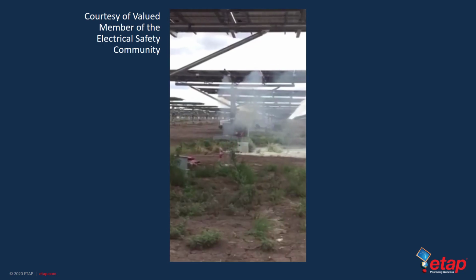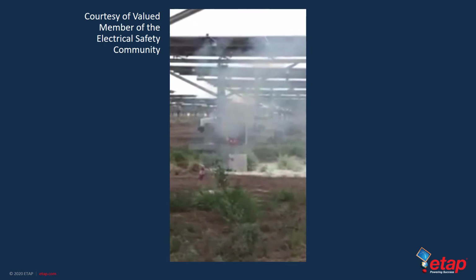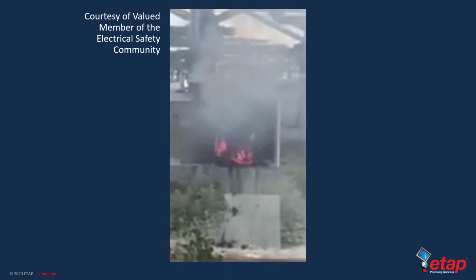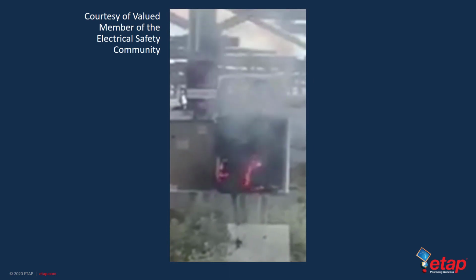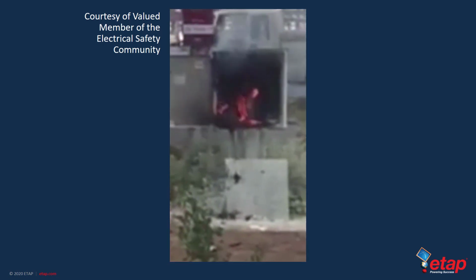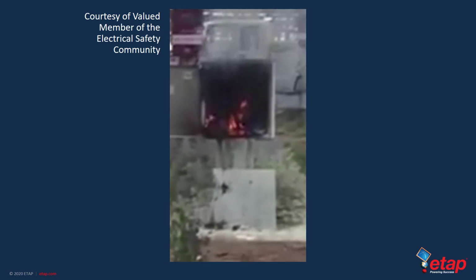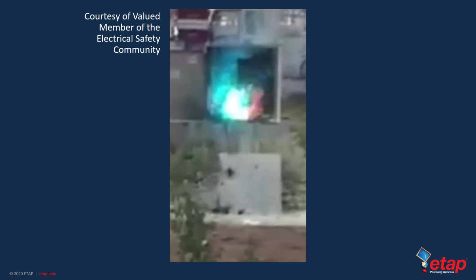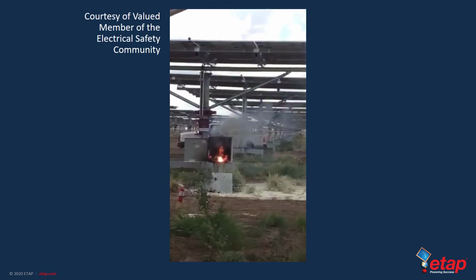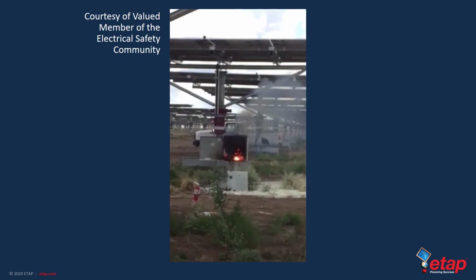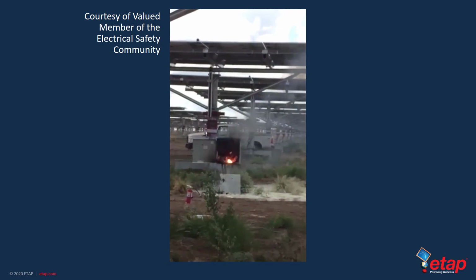This is a very interesting video because it validates a lot of the initial assumptions in the calculation. For example, it is not expected for the overcurrent protection to trip, and this is obvious. This arc continues to arc and sputter for a long time. The 2-second rule is often used to estimate such events, and it's very likely that you will end up using that in your actual calculations.